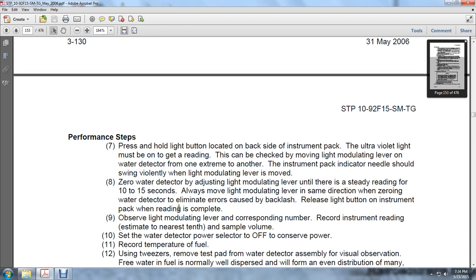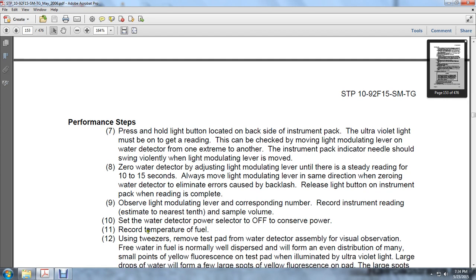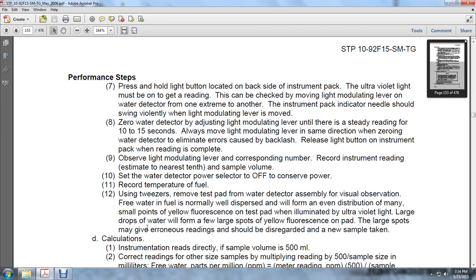Release the light button on the instrument pack when the reading is complete. Observe the light modulating lever corresponding number. Record the instrument reading, estimated to the nearest tenth, and the sample volume. Set the water detector power selector to off to conserve power. Record the temperature of the fuel. Using the tweezers, remove the test pad from the water detector assembly for visual observation.